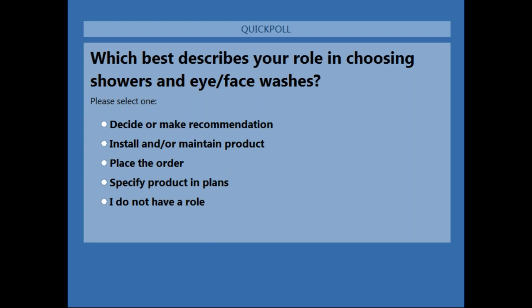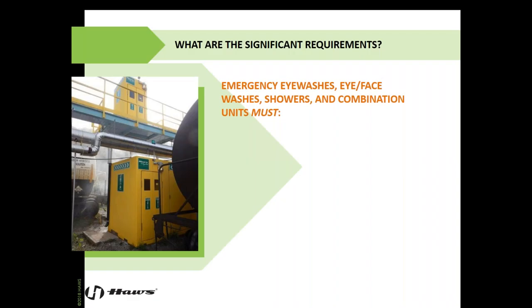Okay, thanks, Sam. So moving on, we're going to go into the significant requirements of the standard. To start with, all equipment, eyewashes, eye face washes, showers, and any combination of those types of equipment, must first be accessible within 10 seconds. Now, all of us are built differently. Each of us is uniquely human in different ways, and not all of us can cover the same distance in 10 seconds. It's different for all of us.